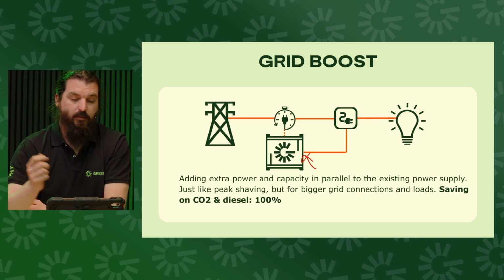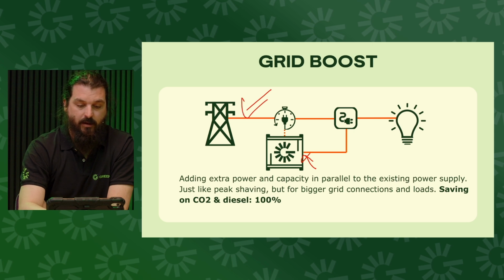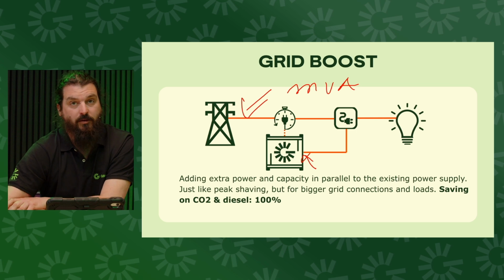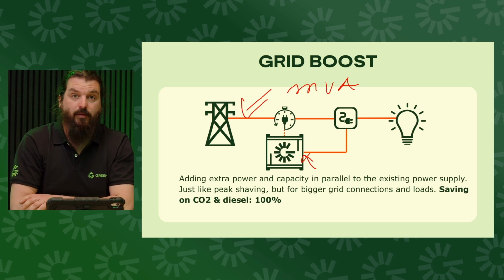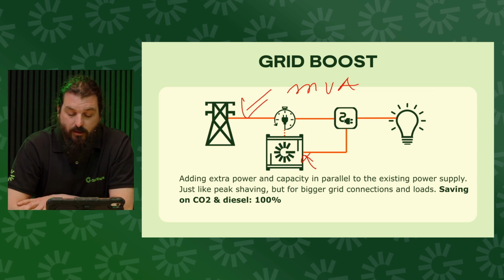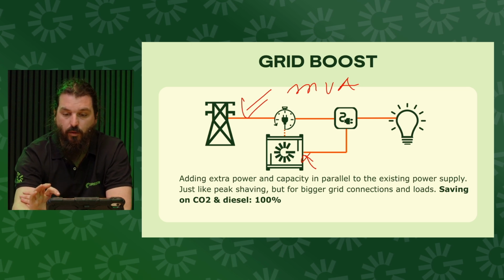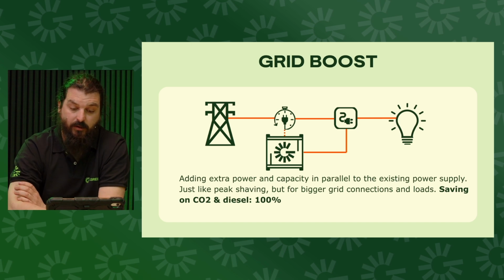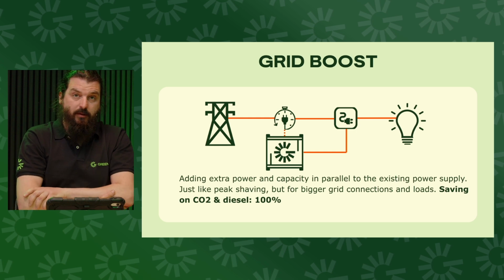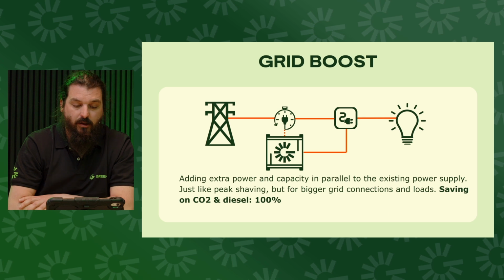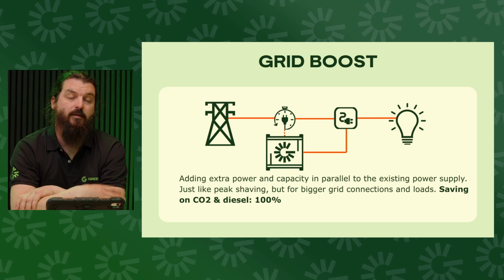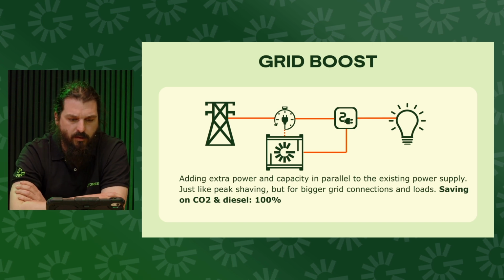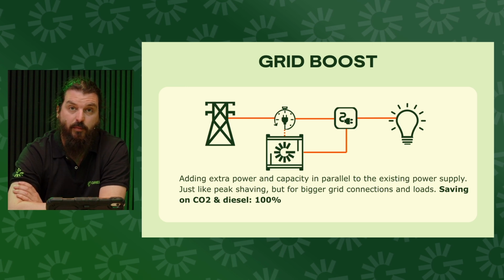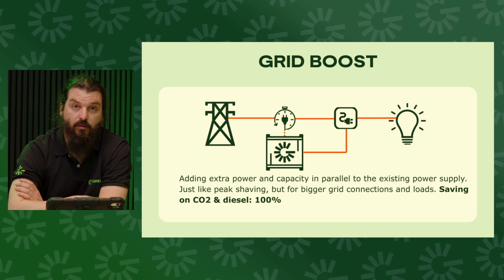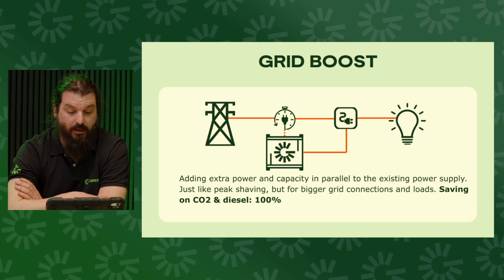But if you then need more energy, so let's say that this grid connection is a multiple MVA connection, obviously that's not going to pass through the battery unless you have a very interesting warm puddle of copper at the bottom of the machine. That's a problem. So instead, we designed a system which will parallel connect a battery to this connection. Obviously, we still need to know how much energy is being drawn from this grid. So this is where we use our external meter, or one of the existing meters which are already at the point of coupling, and integrate that into our EMS, and then send commands to the battery to draw or push energy out of its storage capacity.